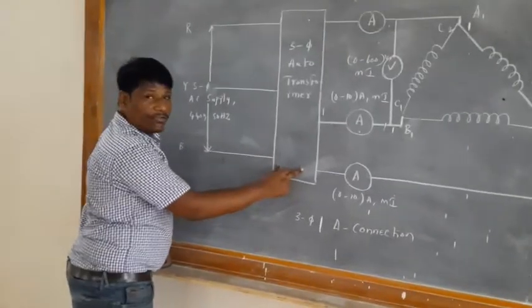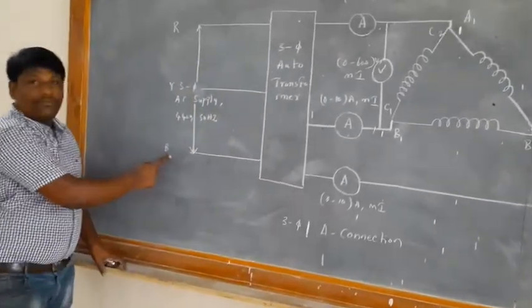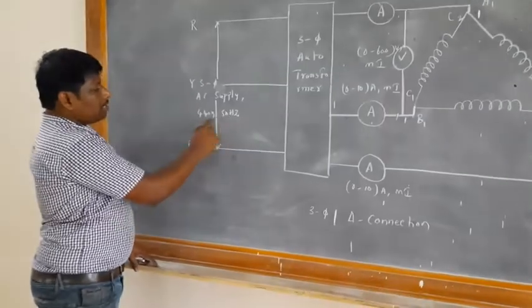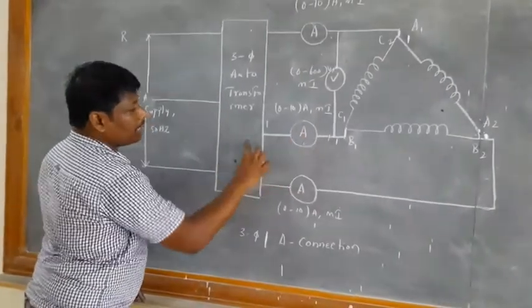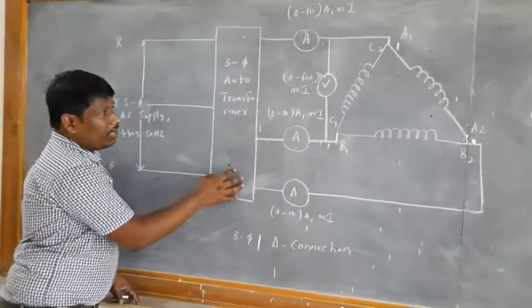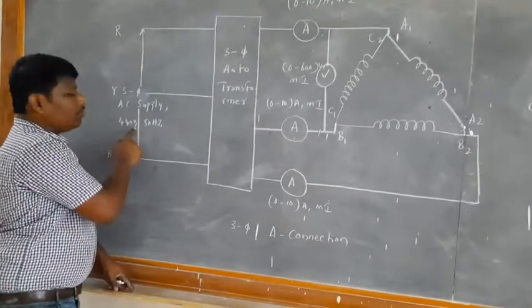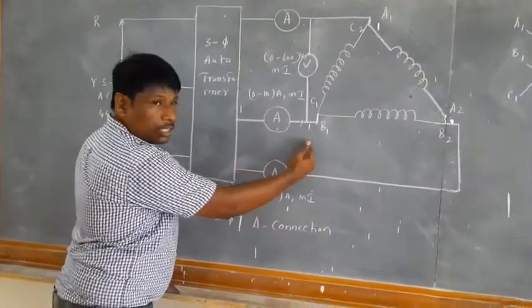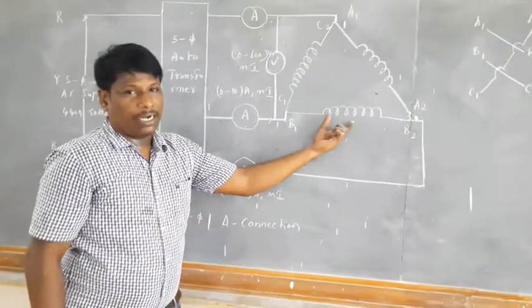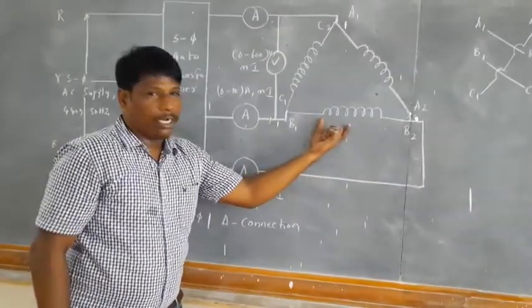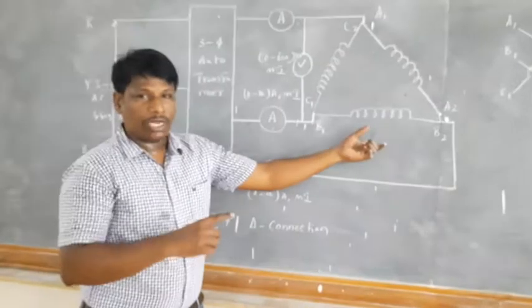This setup represents a three-phase autotransformer to which three-phase electrical input is given. R, Y, B represent the three-phase electrical supply of 440 volts at 50 Hz. The output voltage of the autotransformer can be varied from 0 to 440 volts. Initially the autotransformer is kept at 0 and voltage is gradually increased to the rated value of 440 volts. The load connected in delta is initially kept at 0, with a maximum loading condition of 10 amperes.